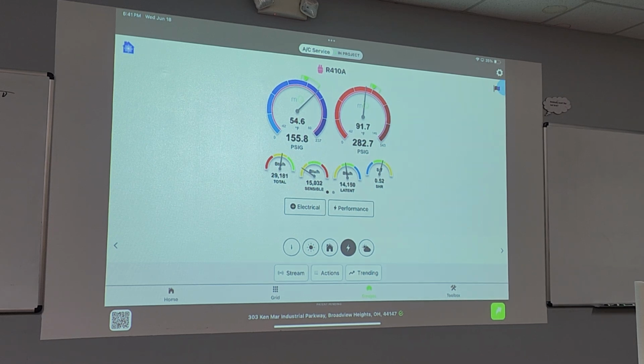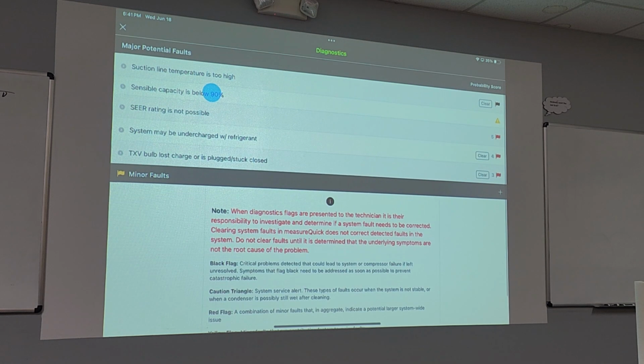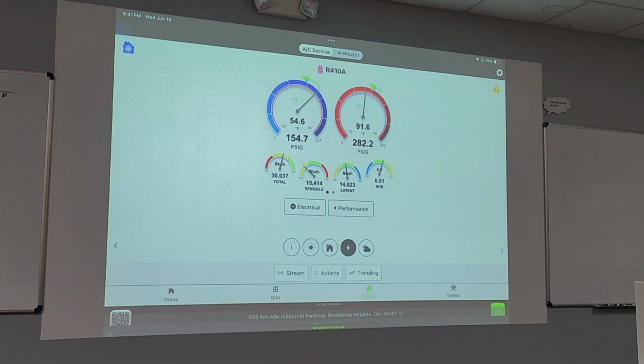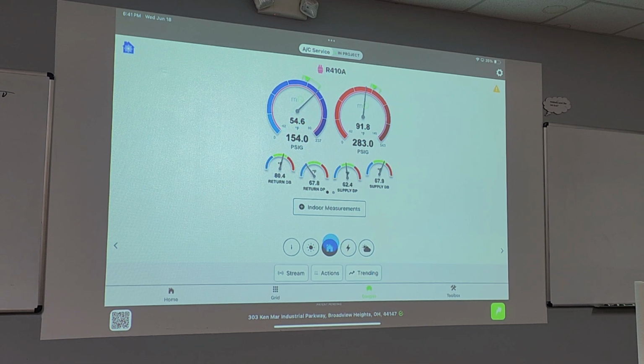When you get the fault code of sensible capacity below 90%, all the horsepower is getting sucked up by dehumidification. You got so much water hitting that coil, it can't make the coil that cold. And just, I mean, look at where the low side pressure is there. You got a 55-degree coil. We're sucking 80-degree air into this thing, and the supply is only 68. It's not even cool, it's not that cold of air.